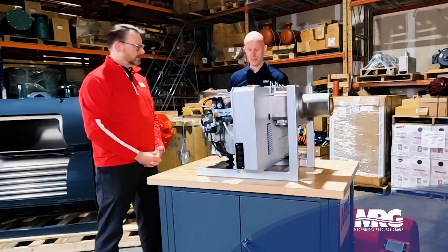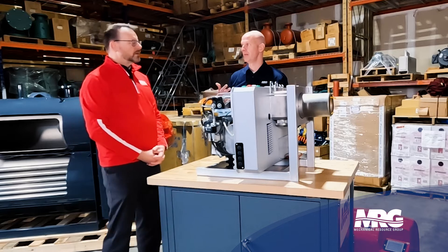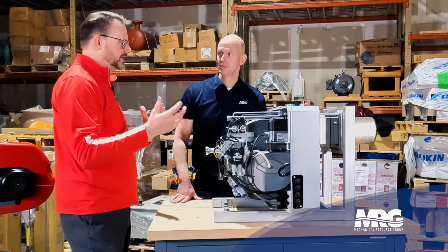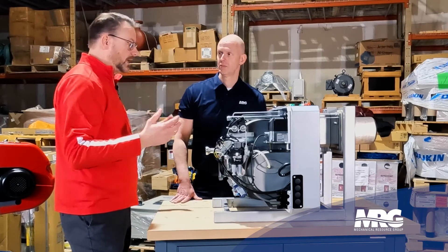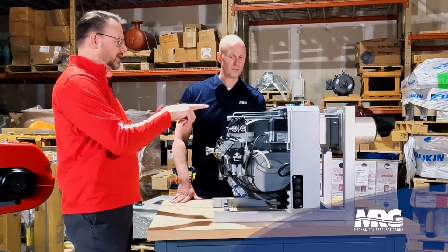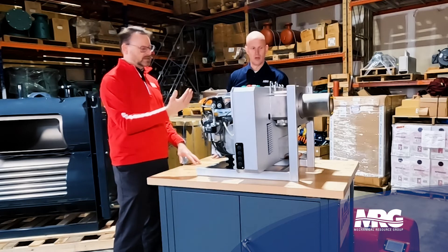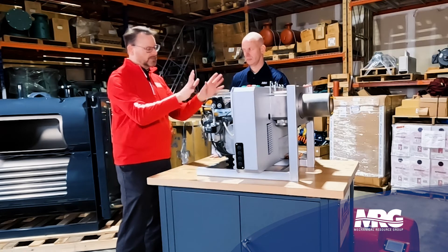I'm really impressed — lots of flexibility. What's the number one thing boiler technicians like about working on Riello burners? Once a technician gets past the fact that they're not working on a more common domestically manufactured burner, they get in front of a Riello and it is a little different — but if they give it a chance, they're going to find it's different in a good way. For example, what this burner does for service is it will pull back on rails and give the technician full access to the consumables: the igniter, the flame rod — giving them access to service and set those components without having to get into the boiler or fully disassemble the burner, which can be a real exercise with other manufacturers. The burner slides back on rails; you access everything you need, work on it, put it back together, and fire it.